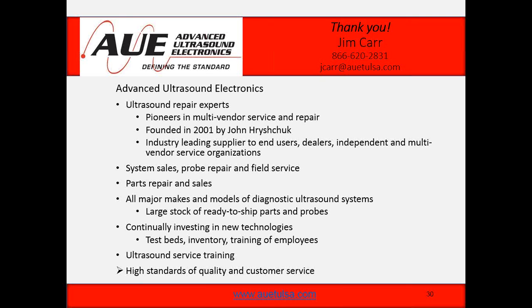Phantoms don't require calibration either, and now there are different qualities of phantoms, and I don't want to necessarily get into each one of the manufacturers, but if you're going to use this as a QA device for doing quality testing, you need a test object that doesn't change. I was saying that the human body may not be the best thing. So there is one brand of phantom, or a couple of brands, that make phantoms that have a liquid-based medium. Anything liquid-based is going to dry out. Right? So one manufacturer, their phantom dries out daily. The other one, it takes a few years, but it's still changing.